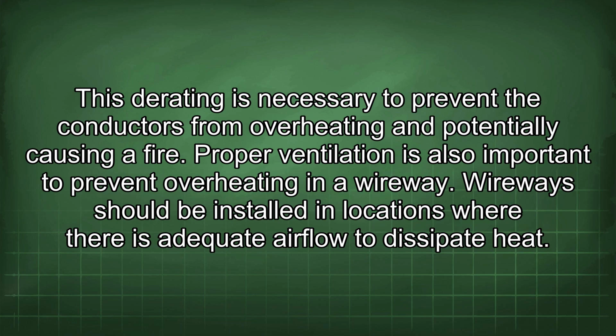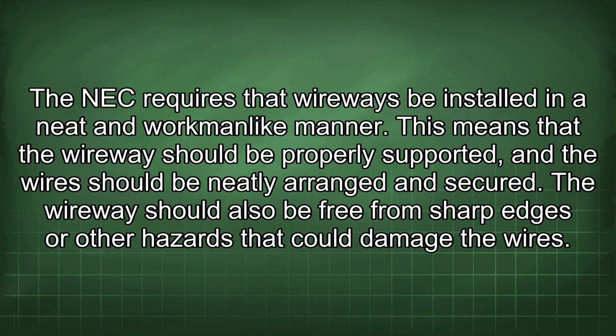Proper ventilation is also important to prevent overheating in a wireway. Wireways should be installed in locations where there is adequate airflow to dissipate heat. The NEC requires that wireways be installed in a neat and workmanlike manner. This means that the wireway should be properly supported and the wires should be neatly arranged and secured. The wireway should also be free from sharp edges or other hazards that could damage the wires.